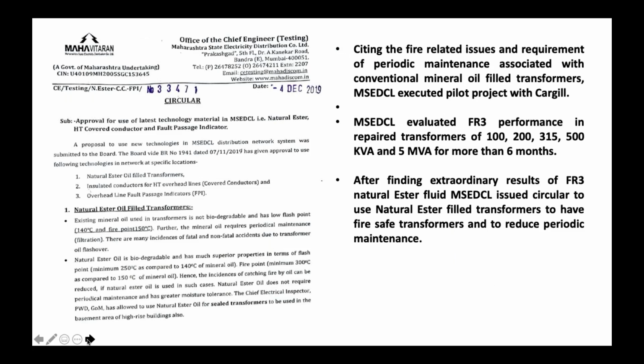Some of the latest developments: the best part is the Maharashtra government has allowed these K-class fluid transformers for indoor installation as against dry type transformers. They understood and took significant trials of it. Some of the experts also visited different locations to see whether they are really fire safe. In IEC it is also mentioned that there has been no reported fire with K-class fluid transformers. So the Maharashtra state government has already released the order that either dry type transformers or K-class fluid transformers can be used. That means both are equally fire safe. That's the government's justification. And in the state of Maharashtra, next slide please.